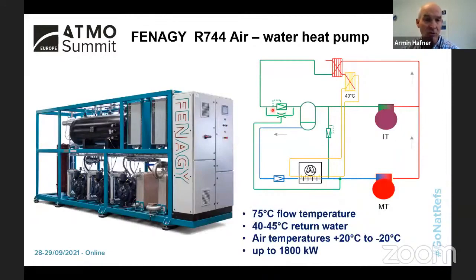We see also a trend to utilize CO2 in heat pump systems. This is an example from Denmark. They produce these kind of racks now for district heating, where air is the heat source, supplying 75-degree water into the system, while the return in Denmark is down to 40 degrees, and it can work in all air temperatures which are typical for the Scandinavian, North European area, from plus 20 to -20. And their systems are able to provide up to 1.8 megawatt per skid. That is very interesting for Denmark, phasing out fossil fuel, and they want to be on the green agenda very soon. And these kind of heat pumps will be more and more installed to supply heat into existing district heating systems. And these units can be switched on at short notice. That's a very good point.